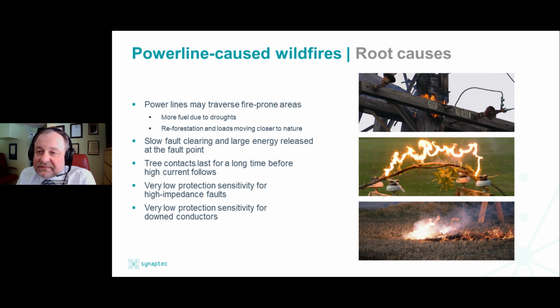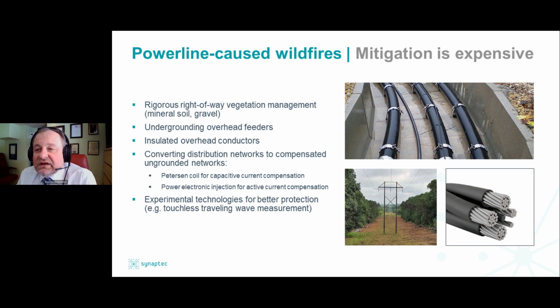down conductors. We all know that there are feeder relays with specialized built-in protective functions that claim high impedance fault detection and down conductor detection. Those technologies have been out there for about 20 years. There is a lot of field experience, and that field experience is not extremely positive. Those technologies do work, but they don't meet the expected requirements to really address the wildfire and public safety issue. When it comes to mitigation, it is expensive.